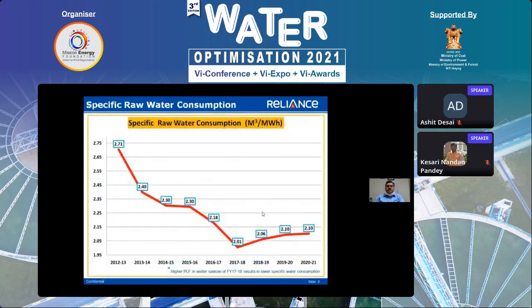The next figures you can see are the marvelous achievement of our plant. We are maintaining around 2.10. In the year 17-18, we went below, up to 2.01. But at that moment, the PLF in the winter season was very high, so the cooling tower evaporation losses reduced drastically in that year. Since we are situated in UP, the seasons are very cold, so in the winter season the specific water sometimes goes below 2 also. So that was an exception in 17-18, but for the majority you can see we are maintaining 2.10, which is well below the norm of 3.5.